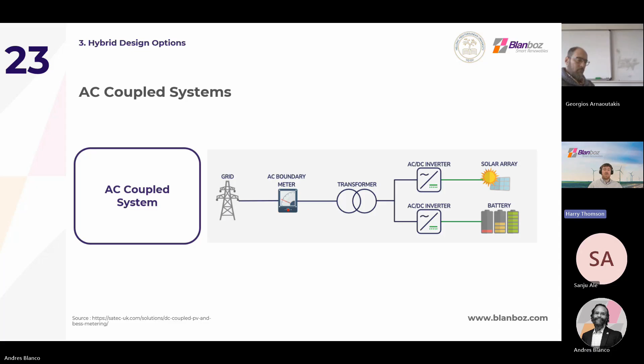Enhanced redundancy as well. If one of the PCS goes down, it doesn't take out large areas of the site, and other inverters will still be up and running, reducing the impact of downtime and financial revenue loss. The disadvantages are the lower round trip efficiency. There's more conversions between the array and battery, leading to more losses. The site is also more complex. There's more equipment and inverters to synchronize and manage, and this leads to more sophisticated controls being needed to control the overall site.